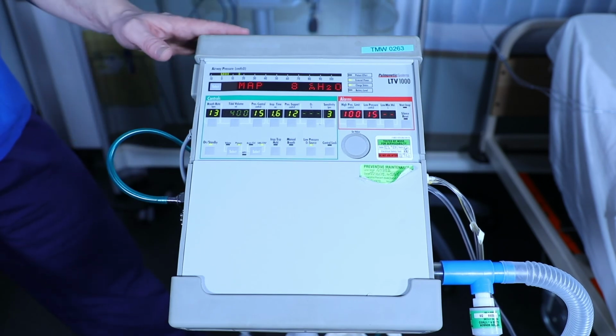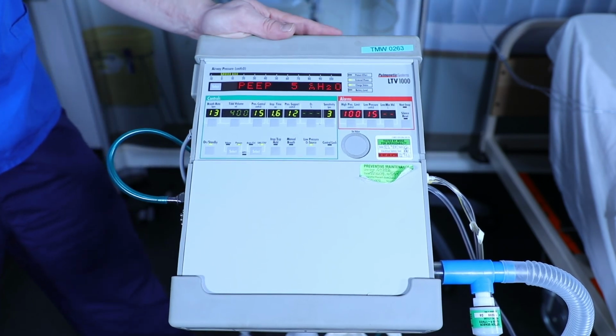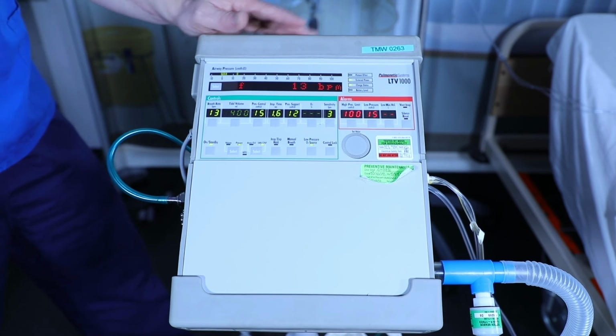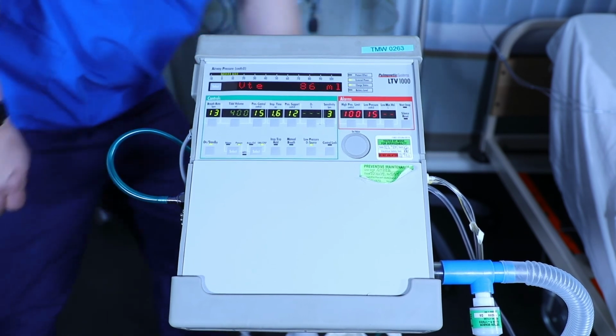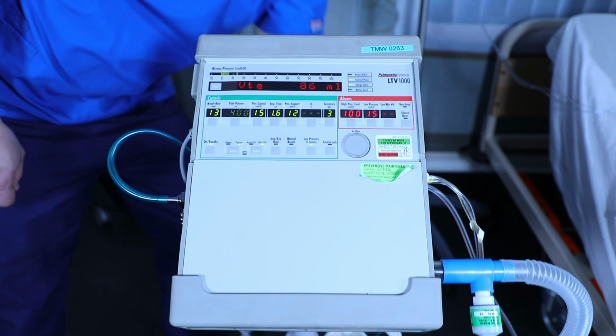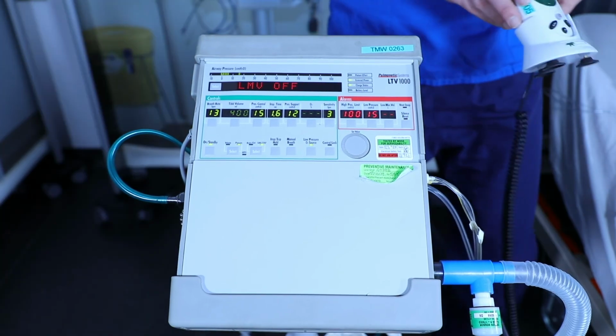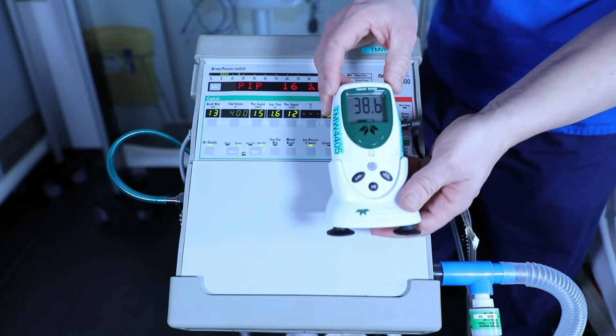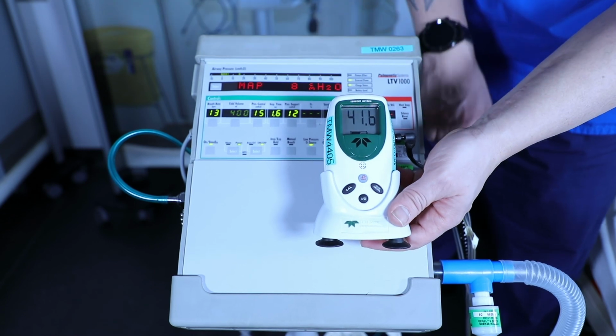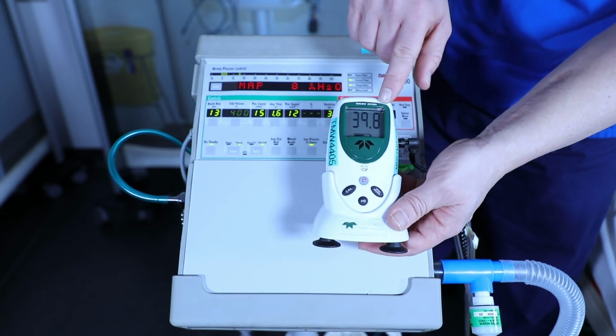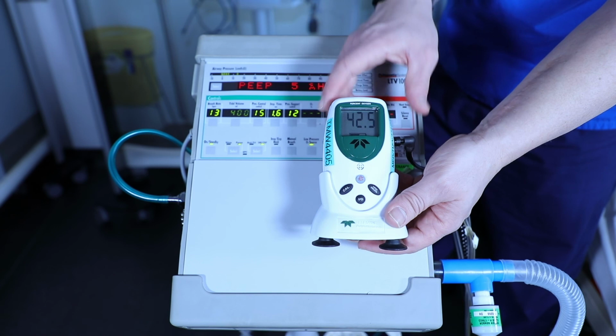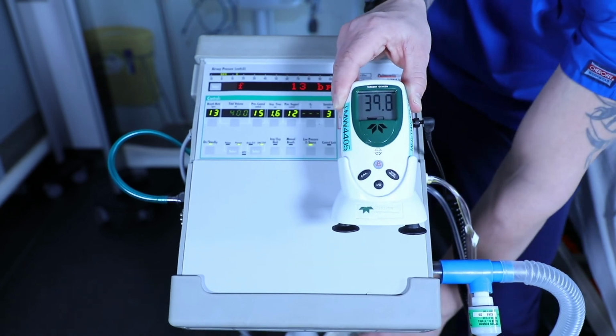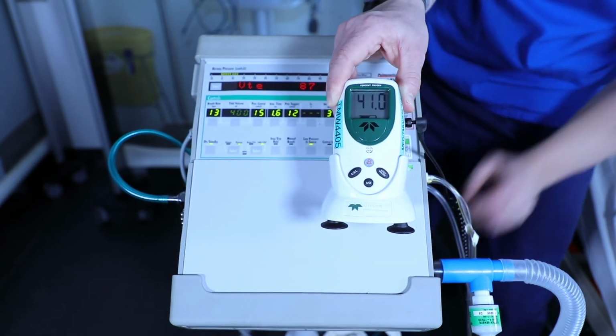To deliver an increased oxygen flow more than room air, we change the cylinder to the appropriate litres per minute. With the O2 analyzer attached, you can see that setting the cylinder to 2 litres per minute delivers approximately 40% of oxygen. To increase this, we just simply increase the flow rate of the O2 cylinder.